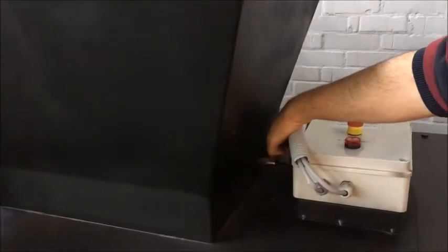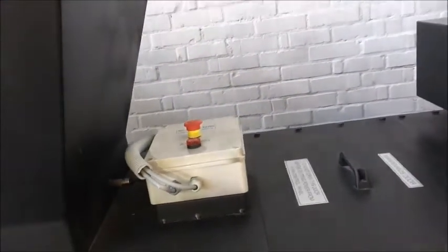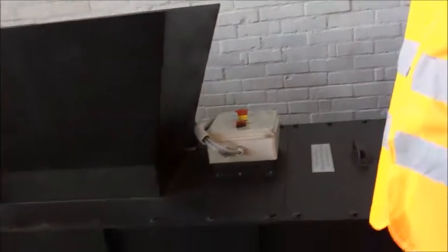This one checks the load of the inlet, and when the garbage container compactor is full, the RAM is activated by the photoelectrical cell. With pistons, the garbage is pushed inside the container, which is locked to the compactor with the locking mechanism. This activation continues until the container is fully loaded. Now I am going to show you the functioning of that one.